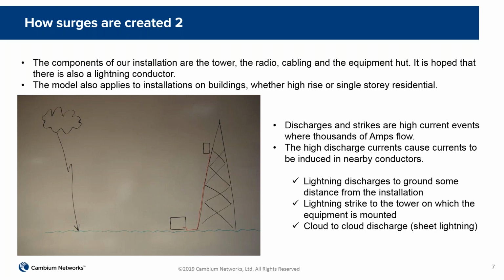In this case, we've got a radio on the tower, and a cable down to the hut at the bottom, and so there's coupling from the surge, wherever the lightning occurs, to that drop cable.